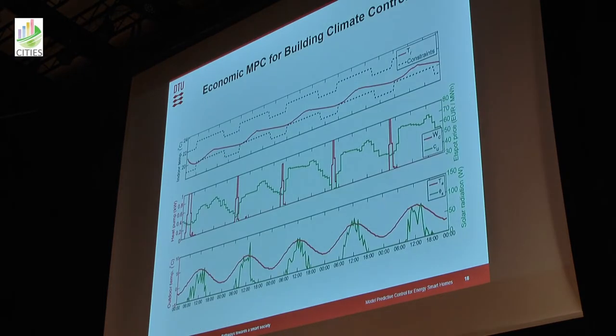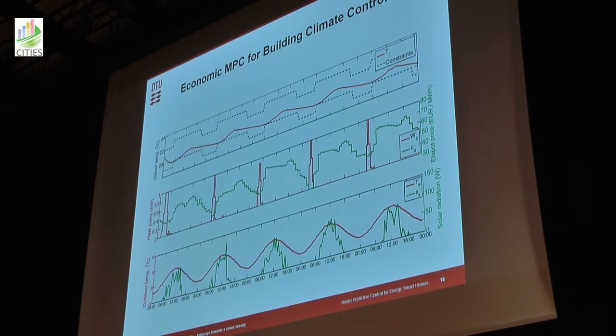What do the solutions look like? This is a result from work by Rasmus Halvor — here you only have the house with the heat pump. You can see the solar radiation, the ambient temperature, and the electricity price — it's cheapest at certain times. The model predictive control decides when to turn the heat pump on, and you can notice it's always when prices are cheapest, while keeping the temperature within the bounds specified by the user.